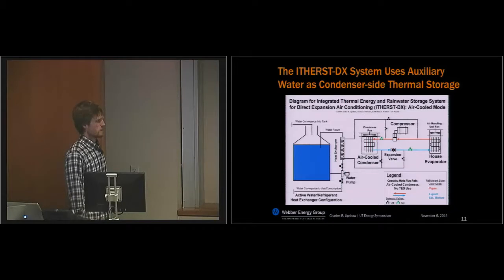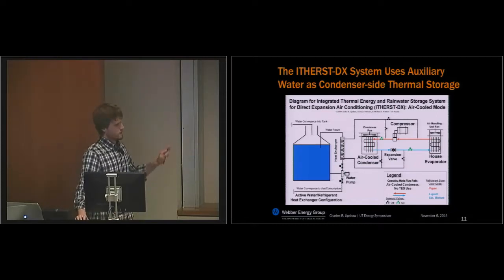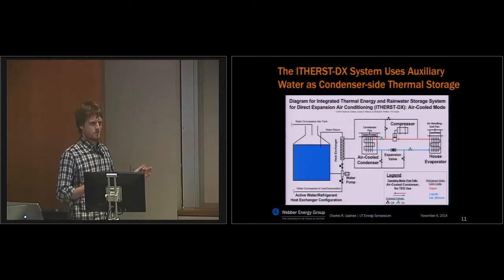So that's how you get a nice low temperature in your evaporator. You then boil this saturated mixture at about 40 degrees Fahrenheit or so, and then all that vapor goes through, and that's the traditional air-cooled direct expansion system. The system operates in that mode during the morning hours and early afternoon, before the peak time period of 3 or 4 to 7 p.m.